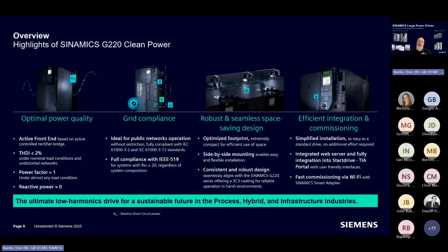If you compare this to the installation of a drive with a filter, or even a commonly available active front end drive from another manufacturer, you'll find that because we're using this different technology, this is really, really compact. Against a filter, you could see maybe an 80% size reduction. And again, it's a Siemens drive, so it works into that Siemens integrated world. If you've got a Siemens automation system, it's going to be absolutely effortless to install using the TIA portal system.